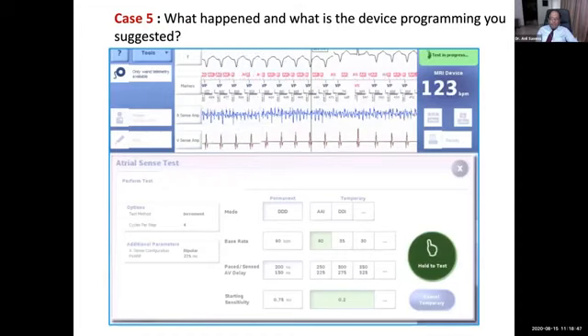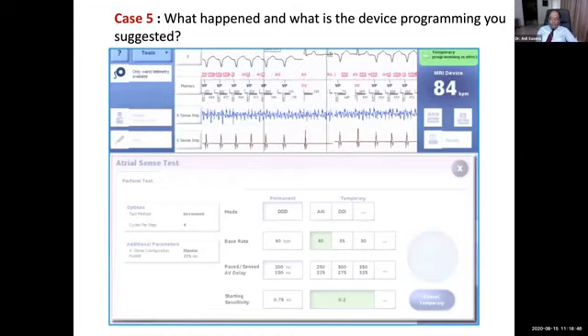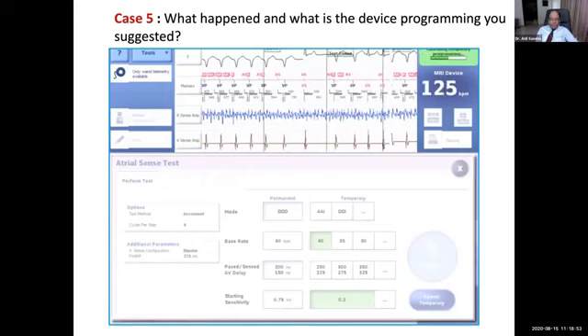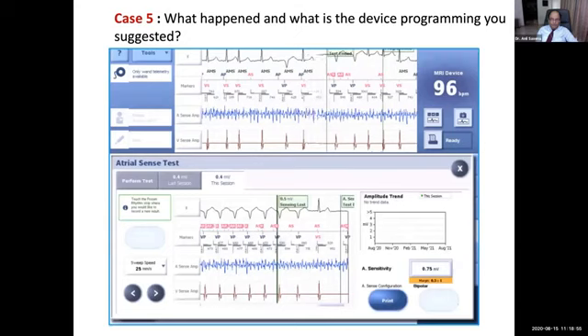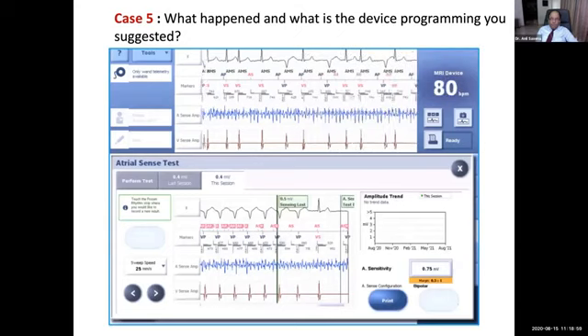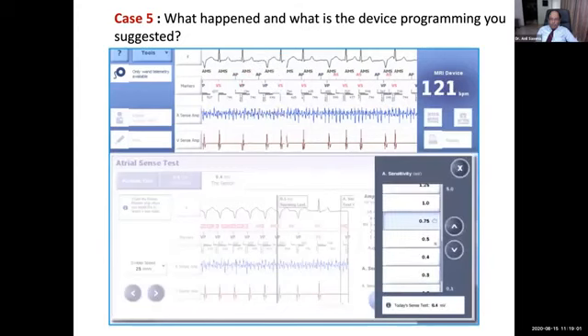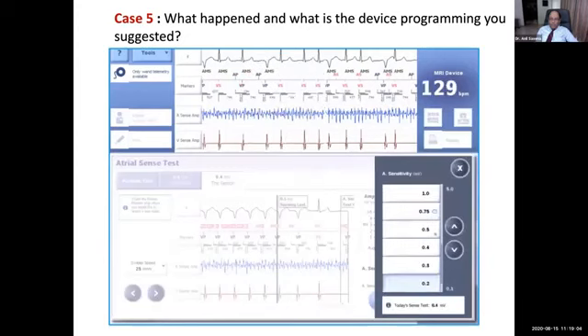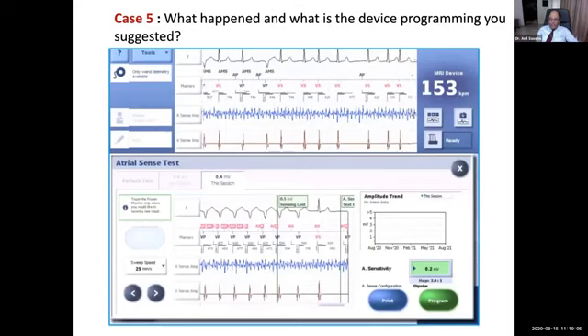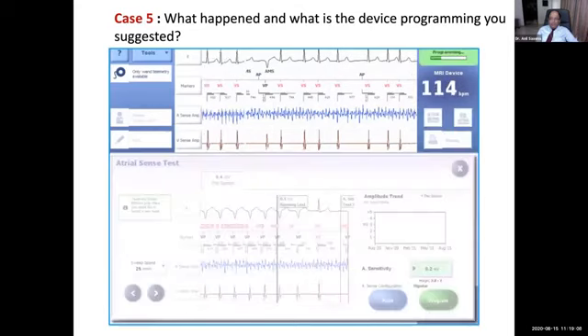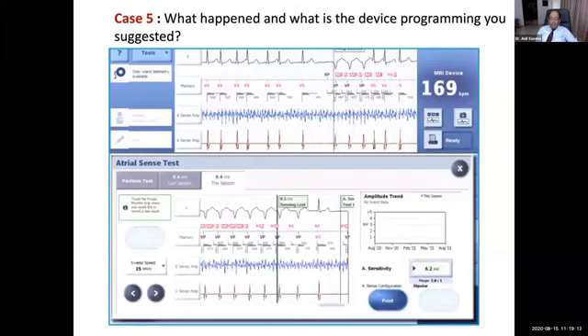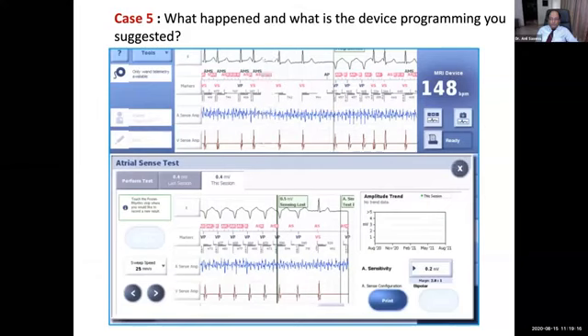So in this example, it was around 0.3 or 0.4, and the sensitivity setting has been then changed. So yeah, at 0.5, the sensing was lost, so it was 0.4. So we changed this to 0.2, and we program it, and that's how it works. So programming is complete, and the patient will then have proper sensing and automatic mode switch.